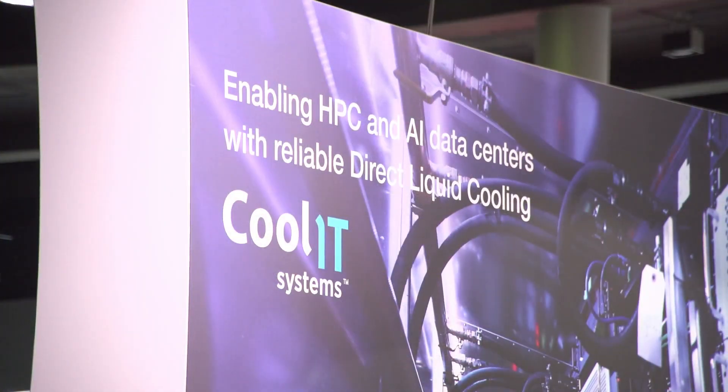That's great because a lot of these processors have a lot of power — 300 watts or more. They do, and it keeps climbing every year. We're also seeing customers ask for a higher percentage of energy managed into the cold plate system. So along with the general CPU and GPU cold plates, we're also offering cold plates for memory, so the DIMMs are completely cooled, as well as different chipsets and FPGAs. Typically 85% or higher of load is now managed.